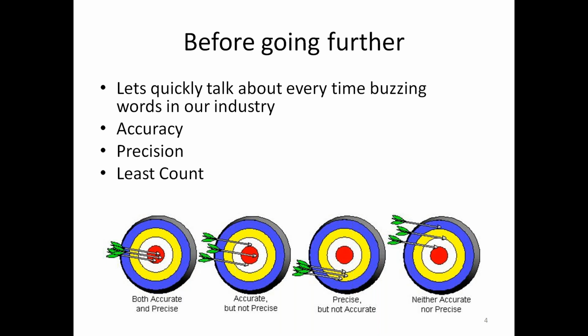The same way, if our instrument is measuring something, our expectation is that it should measure the true value, right? So the true value should not be confused with the drawing dimension. Suppose on the drawing, the distance between the two circles is say 20 millimeter, and the tolerance is say plus minus 50 micron. If the instrument shows 20.030, that means 30 micron more, it doesn't mean that the instrument is bad. We must have calibrated that instrument against some master value. If that instrument achieves that master value, that means the instrument is accurate.